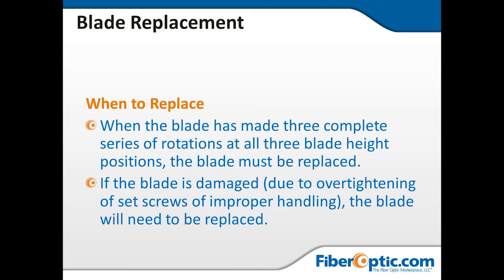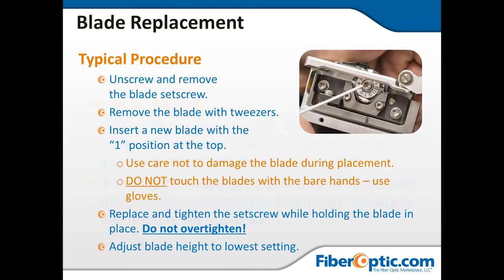Typical procedure, blade replacement. Unscrew and remove the blade set screw. Remove the blade with tweezers. This is the only time you will be able to touch the blade with tweezers, when you are replacing it. Insert a new blade with position 1 at the top. They go from 1 to 12 or from 1 to 16. Always 1 is pointing straight up.